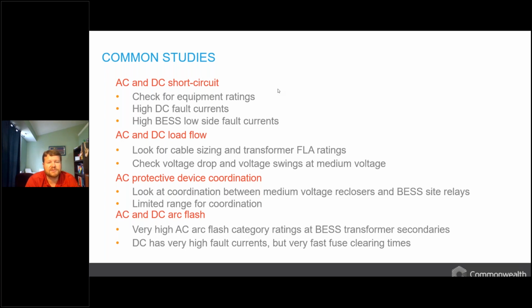We also do load flow studies, and load flow studies are really focused on two major things. We want to make sure that the cable sizing and the equipment are appropriate for the ratings of the equipment. For example, you don't want too small of a cable to handle the normal maximum flows for one of the battery applications. It's important to look at different conditions like low voltage, which may drive up current a little bit.